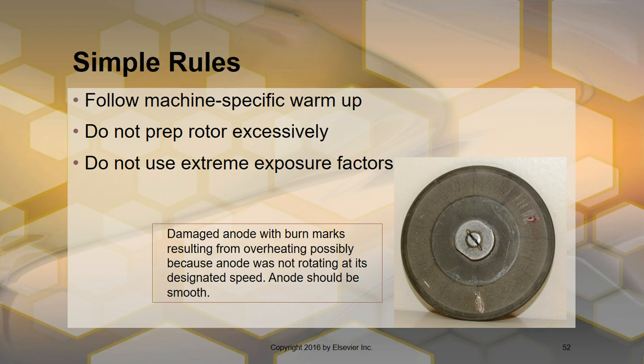The second one is, do not prep the rotor excessively. Every time you prep that rotor, you've actually warmed it up and you're making the heat build up a little bit more. So the best thing is to press the prep and the exposure at almost the same time.